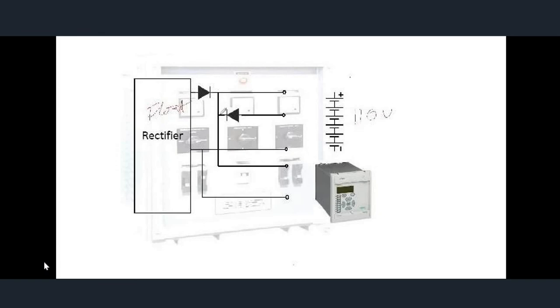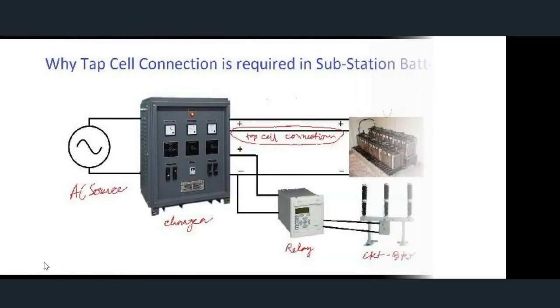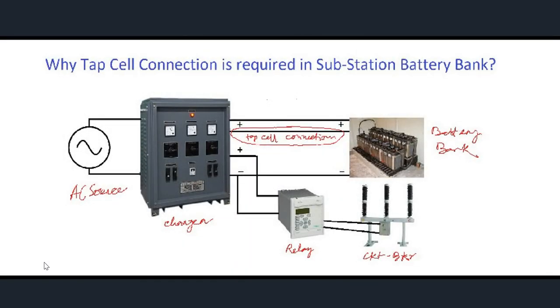With this contactor closed and with boost mode on, this contactor will open and the load will get voltage from a lower potential of the battery coming through the tap cell to the load. Hence it is clear that the tap cell connection in batteries is done to protect the DC loads — that is, relays, circuit breakers, and any other DC circuit coils — from overvoltages when the battery charger goes to boost mode. Friends, if you like the video please like, share, and comment, and don't forget to subscribe to the channel.